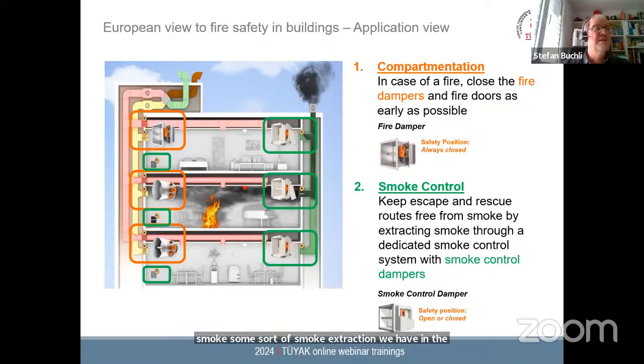What is the reason? The design of the system is completely different. The design of a ventilation system is more towards air quality in a building, and the design of a smoke control system is clearly towards smoke extraction. And smoke means you have a very high volume, and the smoke is also hot. So you can really extract hot gases via the smoke control system. This is why it's a separate system. It can be very efficient, and you see here the damper construction looks a little bit different. I will come to some details at a later point.